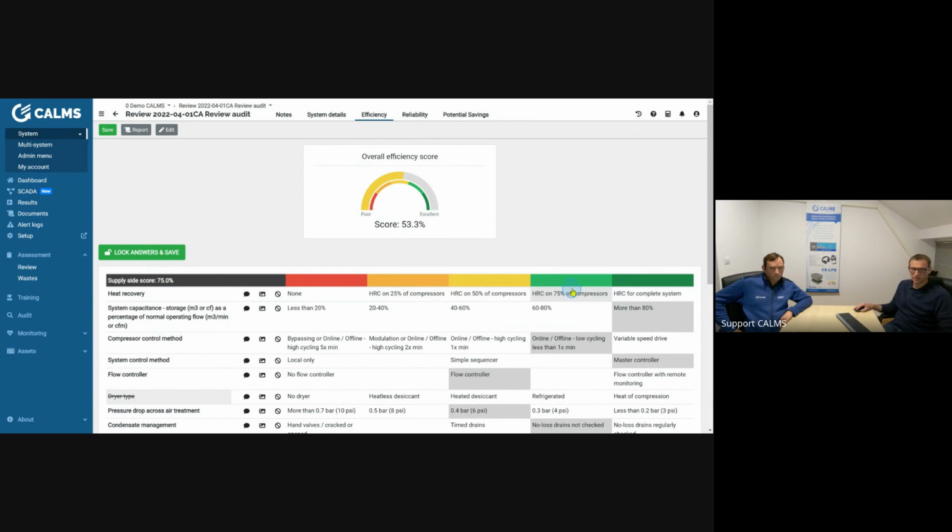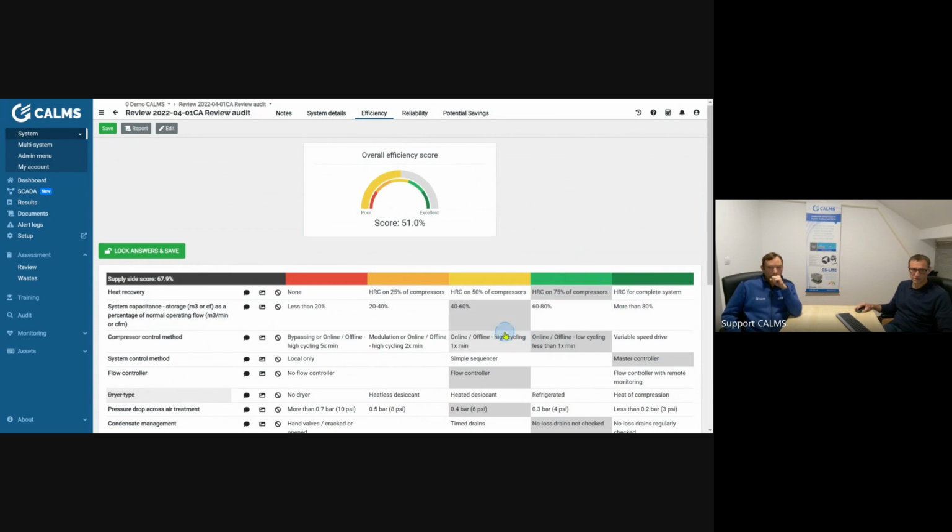So it's at 75%. So we calculated the capacitance, which you said was 80%. But according to what we saw, the 4 cubic meter and how many compressors are running, I would estimate... Yeah, but there are another 2, but they are not very big. Okay. Based on the calculation, we come close to 50% of the storage capacity in your system. So we will use this number. And maybe when everything is replaced or a new receiver is added, we will come to a better method.